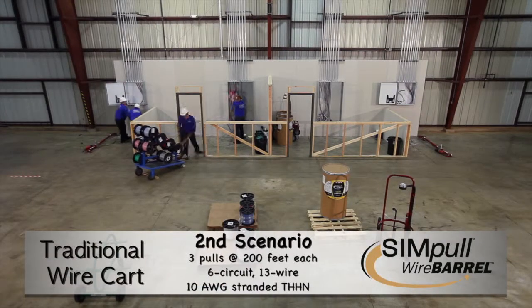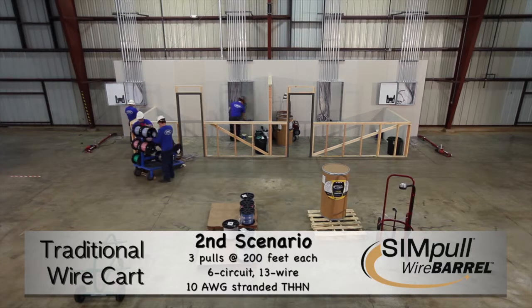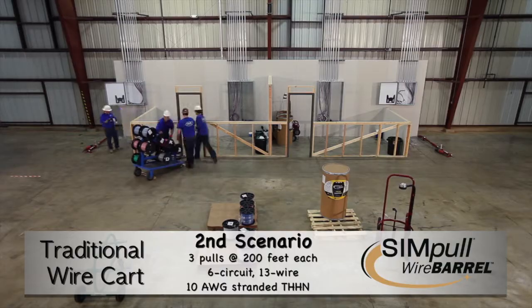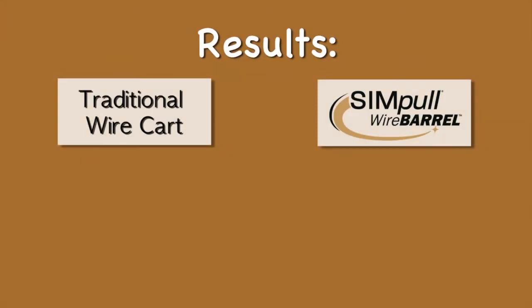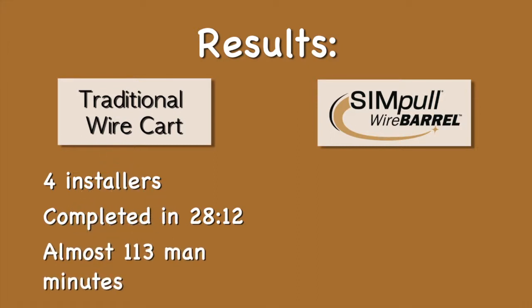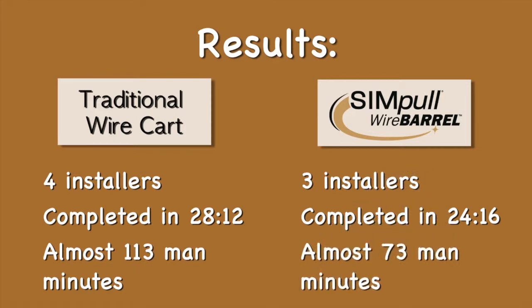This can result in loose wire, creating a bird nest effect or wire jumping off the reel and getting caught on the reel shaft. These issues are virtually non-existent with the SIMpull WireBARREL method. The results of the second comparison show that four installers using the traditional wire cart method completed their pull in 28 minutes 12 seconds, a total of almost 113 man minutes. The three installers using the SIMpull WireBARREL system completed their pulls in 24 minutes 16 seconds, or an equivalency of almost 73 total man minutes, resulting in a total manpower savings of approximately 36%.